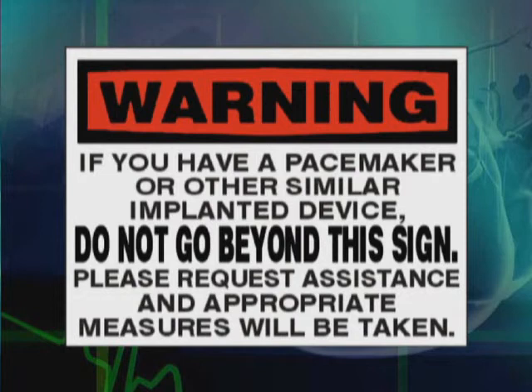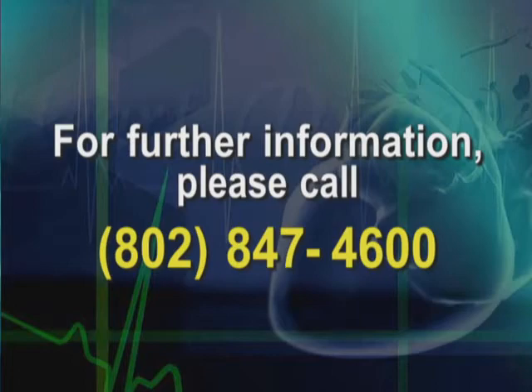That doesn't mean you don't have to be aware of certain electrical fields. Very high-intensity electrical fields can have an effect on the device. For example, patients who use electromagnetic ignitions to start cars, or high-energy switches that might start something like a chainsaw or an arc welding system, can sometimes have high electrical energy associated with them. In those specific settings, we oftentimes don't know whether the energy is enough to cause interference. We provide you with phone numbers to call the company that makes your device, who can provide technical advice on whether these need to be avoided.